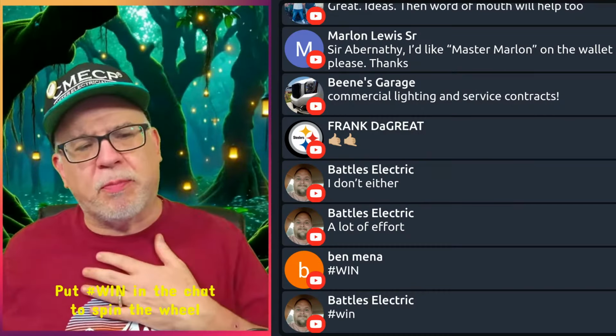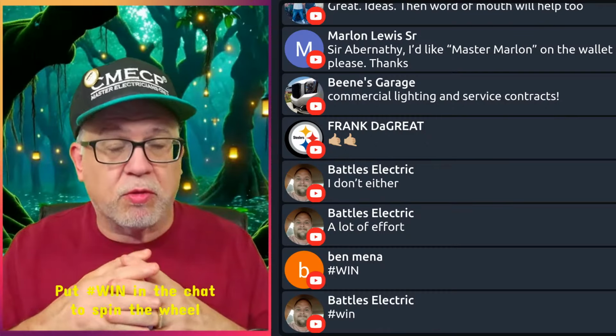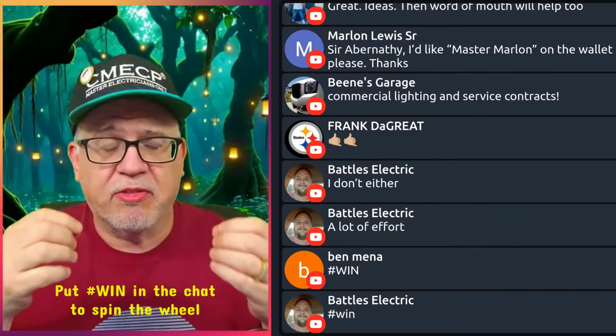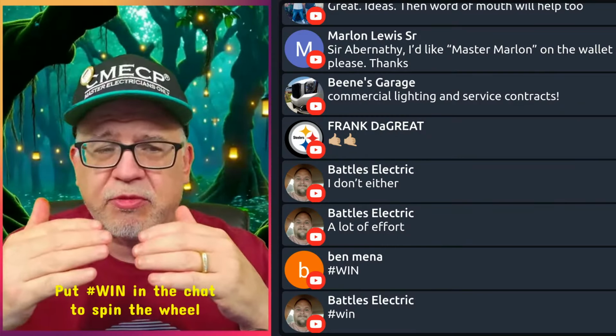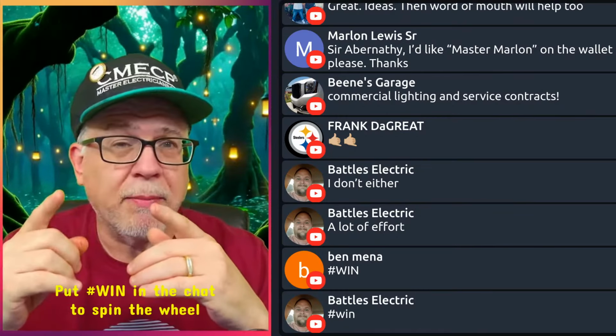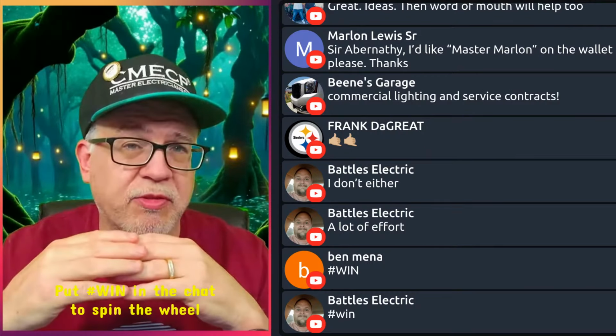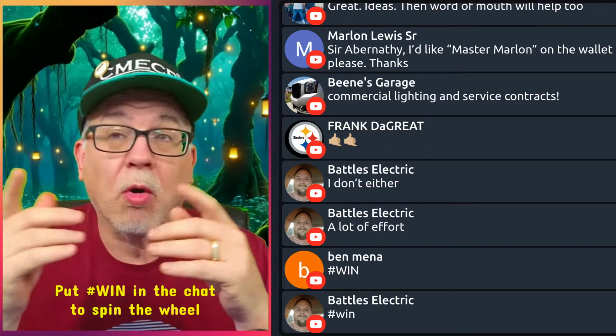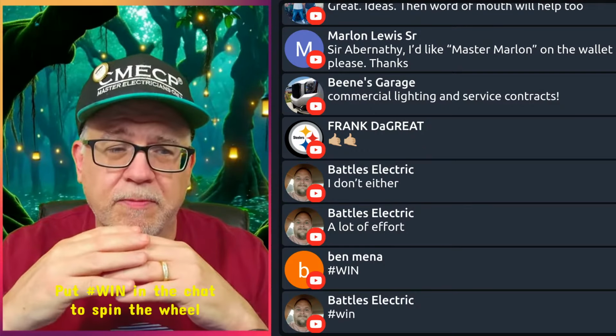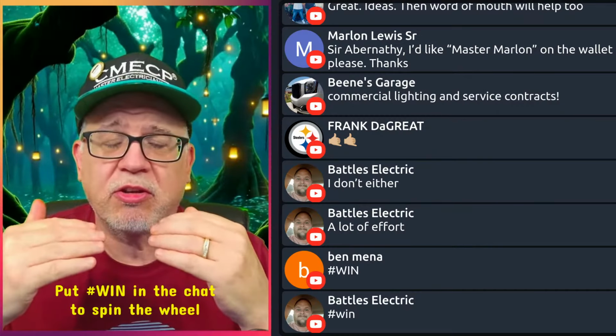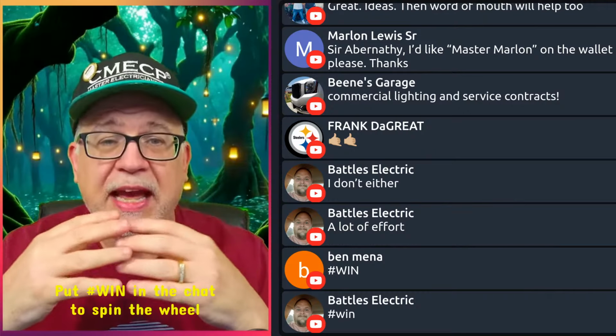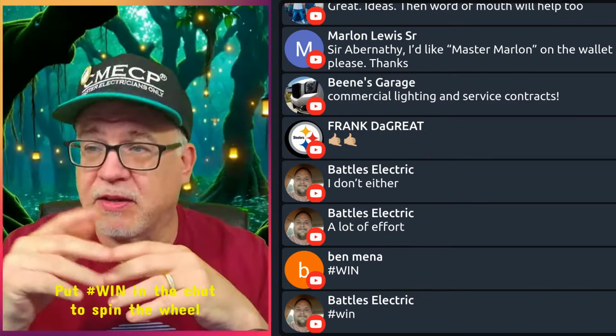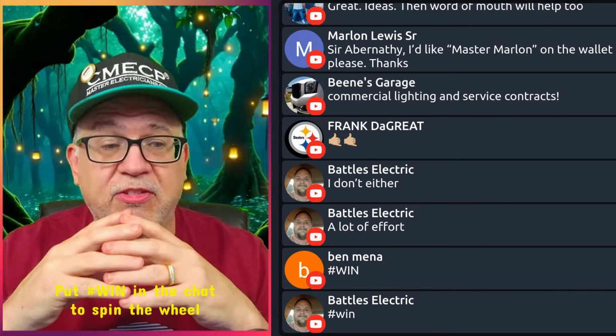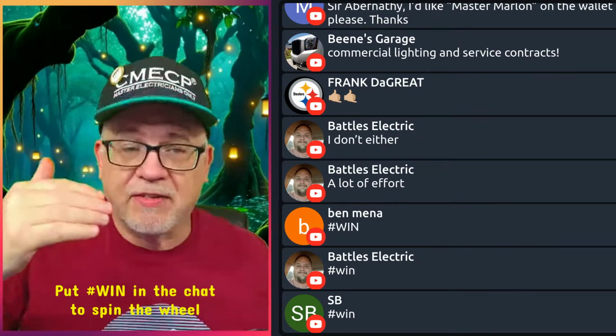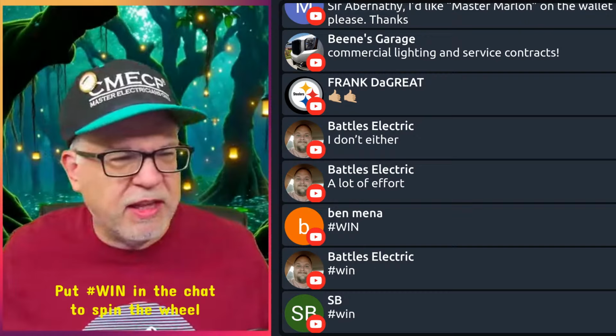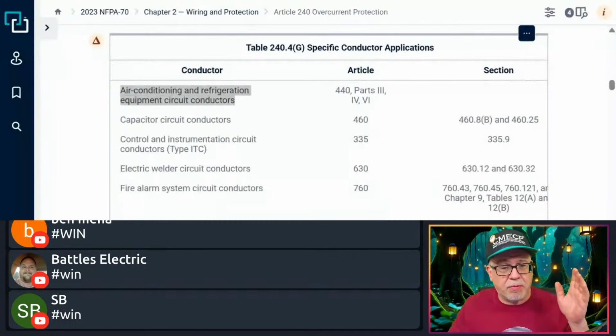But now what we got to do is look at this from a perspective of what do we need? Now, here's the first thing that I want to tell you on this one, makes it easy. Ready, Brandon? You're over 800 amps. So you remember the rule in 240.4(B), which says if you're 800 amps or less, you can go to the next standard size overcurrent device. But remember 240.4(C), which says when you're over 800 amps, the conductors have to be equal to or greater than the rating of the overcurrent device that they terminate into. So just because your calculated load is 920, we cannot use the next size up rule. We have to make sure that we have conductors that are at least 1200 amps because that's the rating of the overcurrent device that we're terminated into, right? Makes sense? Because we don't get to use the next size up rule here. Okay, so in this scenario, if we go to the NEC, and you may have an epiphany, Brandon, while we're watching this.